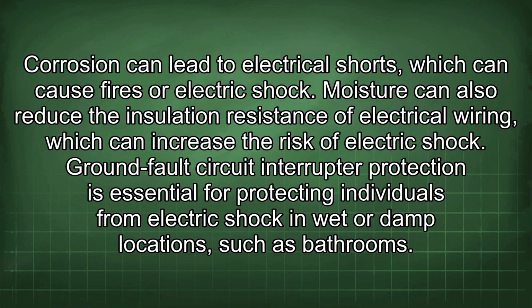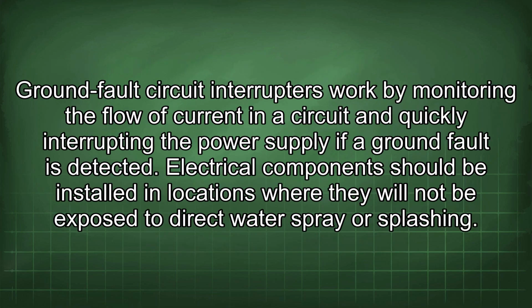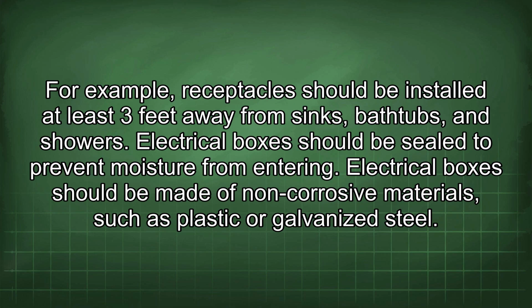Ground fault circuit interrupter protection is essential for protecting individuals from electric shock in wet or damp locations such as bathrooms. Ground fault circuit interrupters work by monitoring the flow of current in a circuit and quickly interrupting the power supply if a ground fault is detected. Electrical components should be installed in locations where they will not be exposed to direct water spray or splashing. For example, receptacles should be installed at least 3 feet away from sinks, bathtubs, and showers.